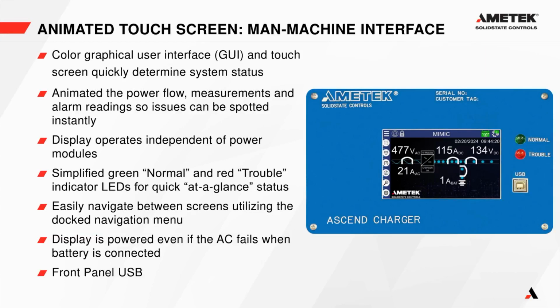The display operates independently of the power modules, so you don't need AC input to operate the display as long as you have a battery connected to the system and the battery breaker is closed. On the front of the screen, we have a normal LED indicator and a trouble indicator. Those are pretty much what they sound like. When your system's running normally, the green LED is illuminated. When there's trouble with the system, the red LED is illuminated, and you also have an alarm buzzer that can be silenced, but by default turns on when a new alarm activates.